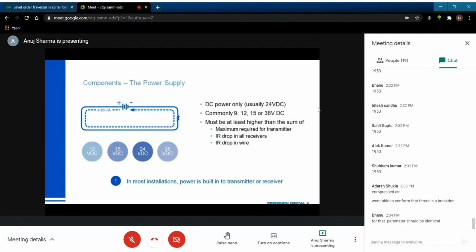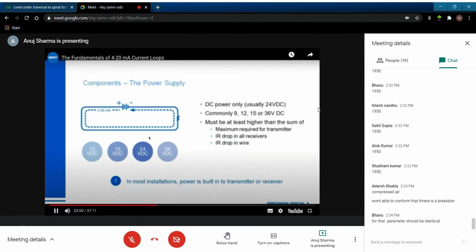So it's critical, especially in cases where you're involving 2-wire devices, that you know what your voltage drops are going to be, so that you know if your power supply is going to be able to support that loop. And if not, you have to look to something else. You either need to get devices that are externally powered by something else other than the loop to lower their voltage drop, or you need to get a power supply that provides more voltage.